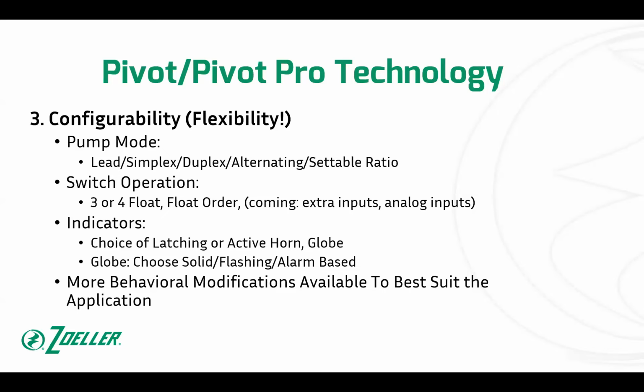And what lead does is, if you've got a lead lag scenario, then you can pretty much, every alternating panel or duplex panel, everybody assumes a 1-to-1 pumping ratio, right? And those of us that have been in the industry a long time have heard the phrase, you want even wear on your pumps. So I own a house, like most of us do, and if I've got a duplex station in my backyard, which means 2 pumps in the pit, I do not want even wear on my pumps. I want uneven wear on my pumps, which goes against what the conventional wisdom has been for the longest time.